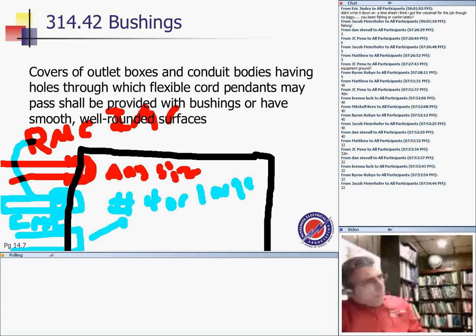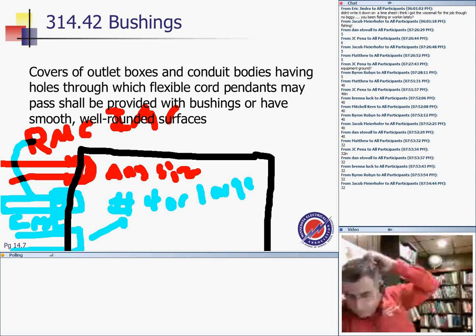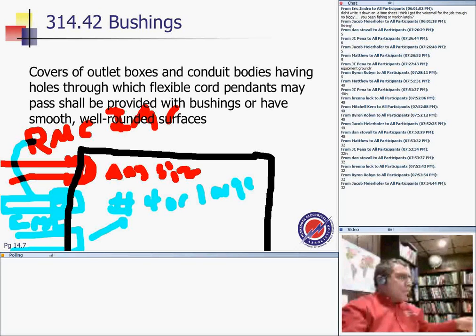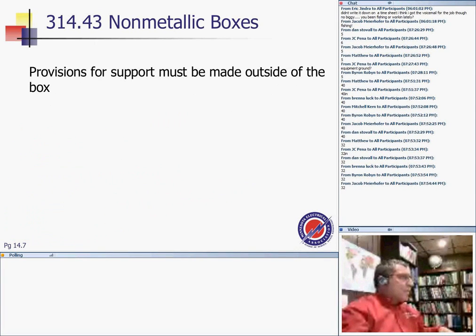Then you apply the rule of number 4. So the key point, Eric, to remember is number 4 or larger, you need insulating bushings. Now, is it wrong to put insulating bushings for everything? No. So that's basically bushings and support and so forth.